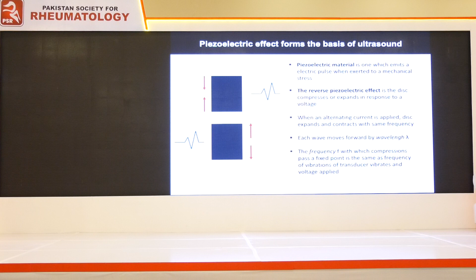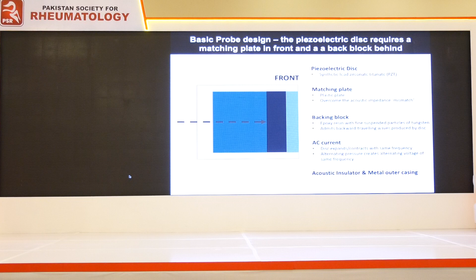So what does the probe look like? Well, this is the basic probe design that you'll have in virtually every ultrasound machine. The darkest blue bit of the probe is actually the piezoelectric disc. Typically it's produced from a material which is lead zirconate titanate, so most crystals are made from this. This is the expensive stuff. This is what makes the probe cost between £4,000 and £7,000 depending on which probe you get. That's the expensive part of the probe, and that's what will shatter if you drop it on the floor. So don't drop your probes on the floor.